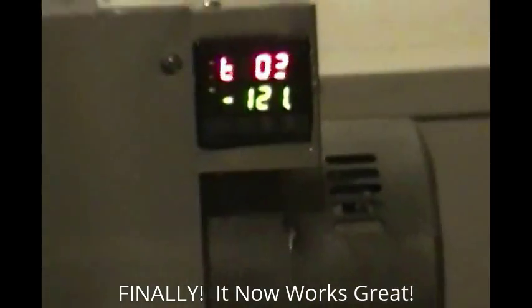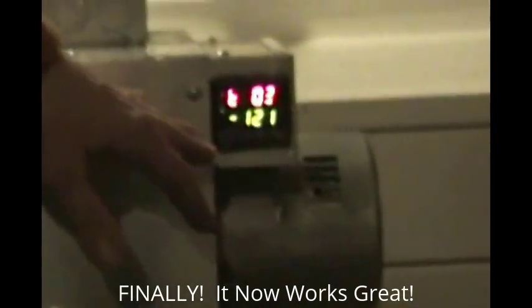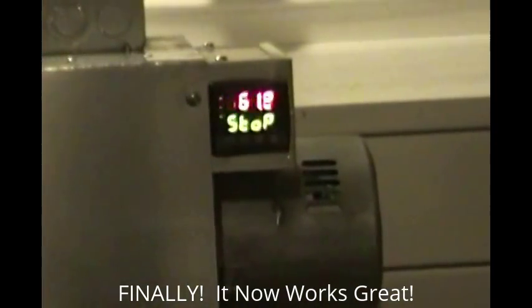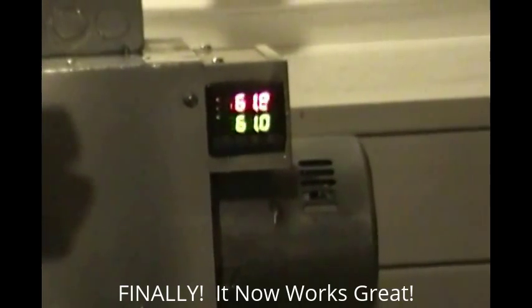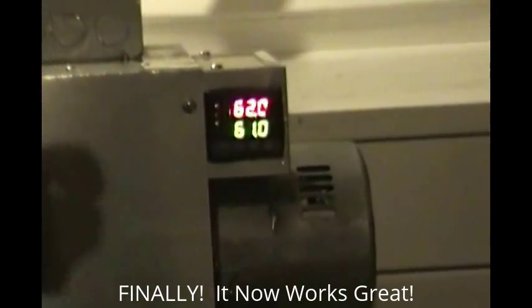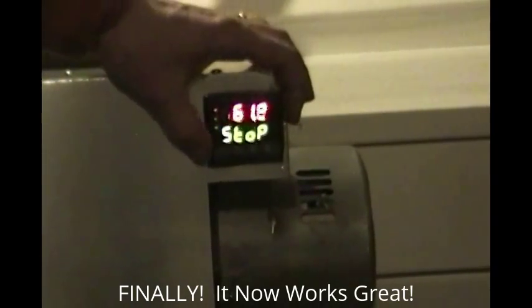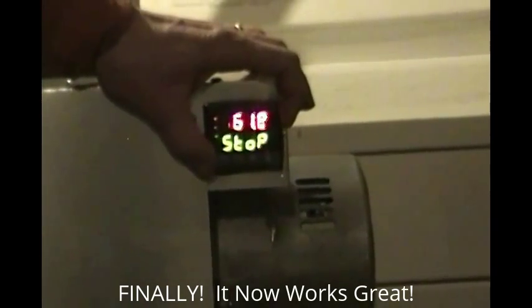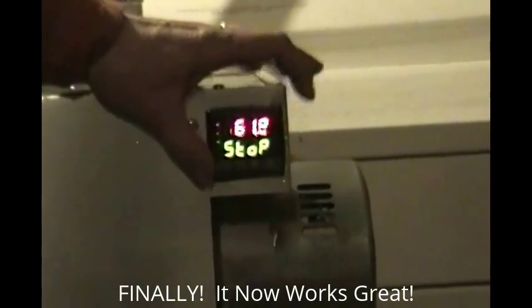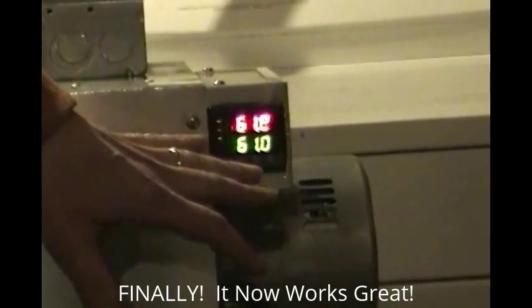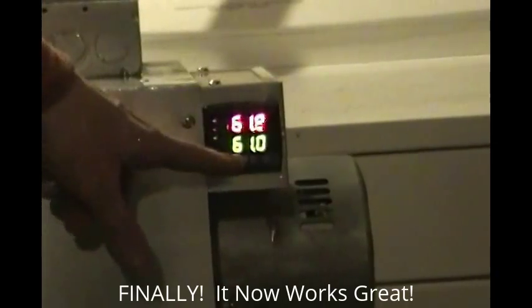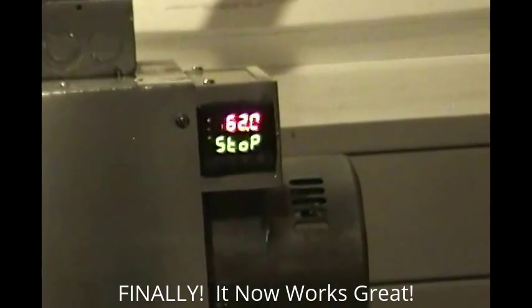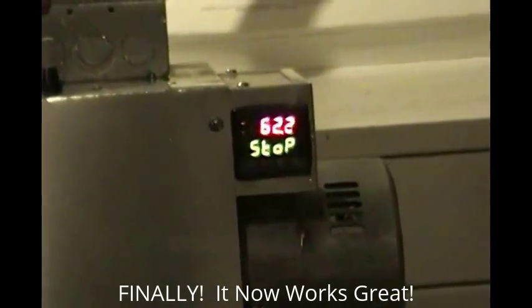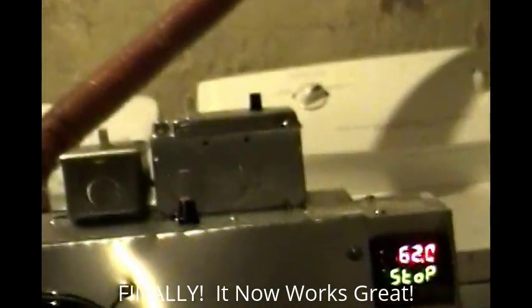The program now, once it hits that last step of negative 121 - again, negative 121 is a specific number programmed into the PID, so the PID knows that once it hits that step it'll say stop, which means it'll turn off the heating coils completely.